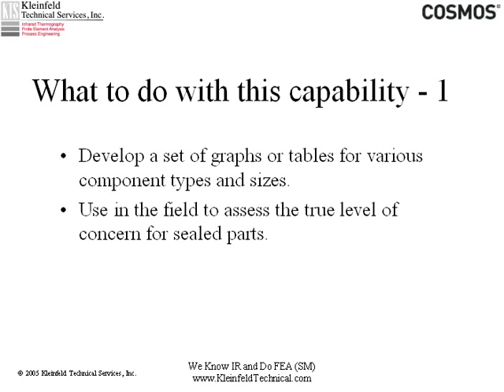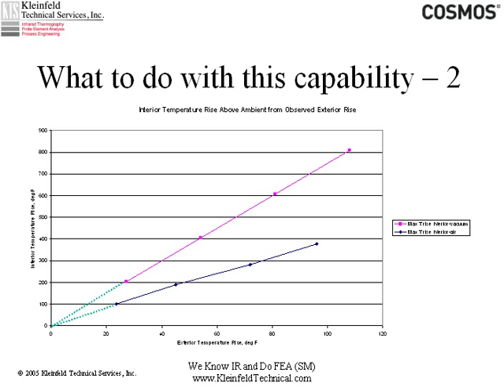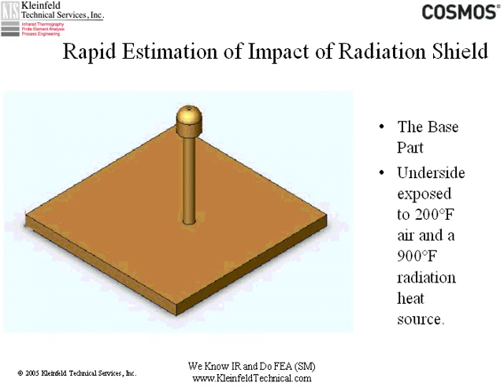Whether the measurement is infrared — as I often do — or a thermocouple, you need to know how to relate one to the other. In this case, you can actually develop a set of graphs to use in the field as guidance. On the bottom is the exterior temperature plotted as a rise above ambient; on the right is the interior temperature as a rise. One curve is for a component that has air in it, and the upper one is for a component with vacuum in it, which has fewer methods for getting heat out. For example, if you had a 40 degree observed rise outside in a vacuum component, you'd be expecting approximately a 300 degree rise at the point of interest.